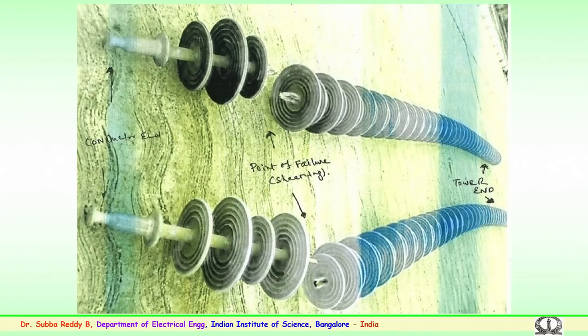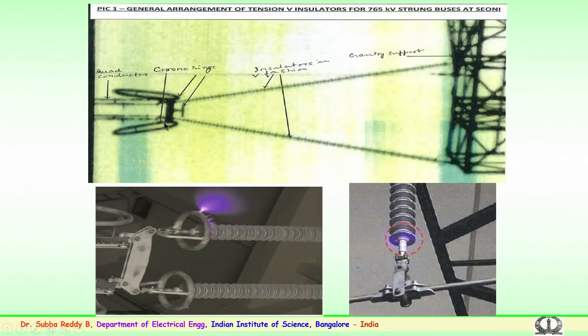This was evaluated, and the reason was the placement of the corona control ring. The placement and the design of the corona control ring, as I mentioned earlier, is very important. The corona discharges from the corona control rings, continuously over a period of time, impinge on the surface. So, this corona control ring causes corona at any instant, and during foul weather conditions this could aggravate, and the entire insulation portion could damage the surface. And as I mentioned, during the mechanical fixing of the end fittings, if there are microstructural damages in the fiberglass rod, water seepage or the radiation from this continuous UV corona could lead to the degradation, and the line gets detached.